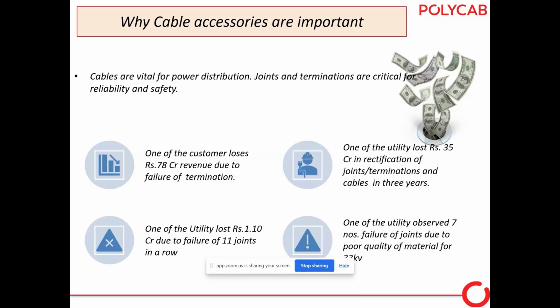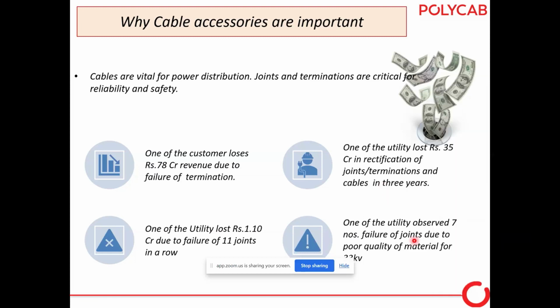Another example is that in 3 years of time, one of the utility lost 35 crores of the revenue. They invested 35 crores in rectification of joints and terminations. Another is that 11 joints failed in a row when they were charging that cable. That's because of the poor quality of the cable accessories. And another example is 7 joints failed within 6 months of time. I will just highlight that area. Yeah. So 6 months of time.